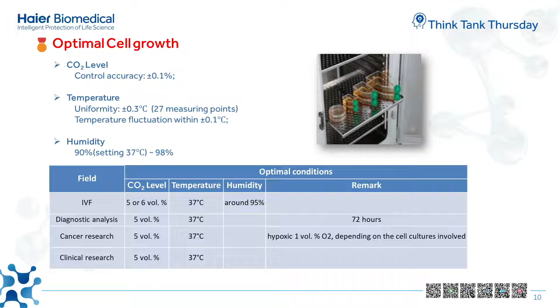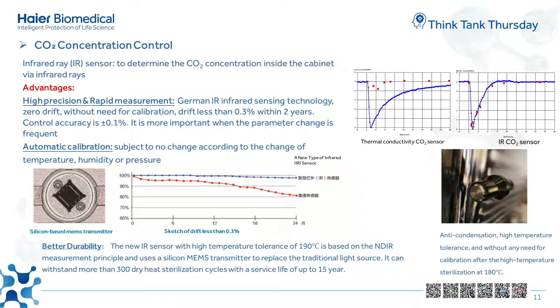In detail, let's see the CO2 levels. We use the infrared ray sensor in the biomedical incubator. The comparison table on the side as well as on the bottom shows the advantage that IR sensing technology brings: high precision, rapid measurement, and automatic calibration convenience to the user. You can see the curve in comparison to an ordinary sensor, and the blue one is the IR sensor.